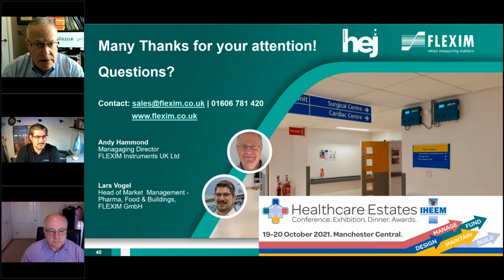Calibration, that's entirely up to the client and how much they need it from their quality management perspective. If you want a recommendation, there is no drift on our meters, so you could say there is no need for maintenance, but a recommendation for those who require it for their quality management systems is that for a fixed meter, recalibrate once every 5 years. We are in the process of encouraging and educating our clients away from recalibration to verification. And we have verification software that will tell you there has been zero drift, zero degradation outside prescribed tolerances since installed. And if you verify it on an annual basis, no need to do anything. And we can produce a verification report certificate. So that's the way we're going with many industries.